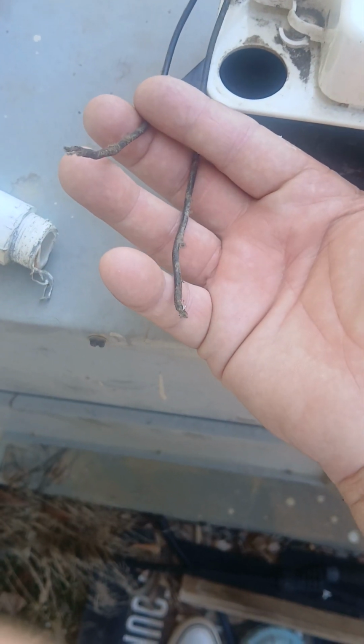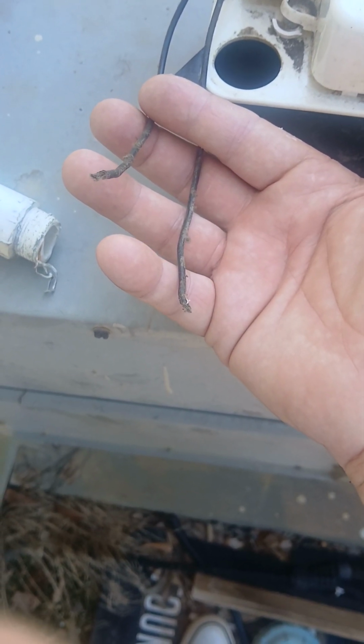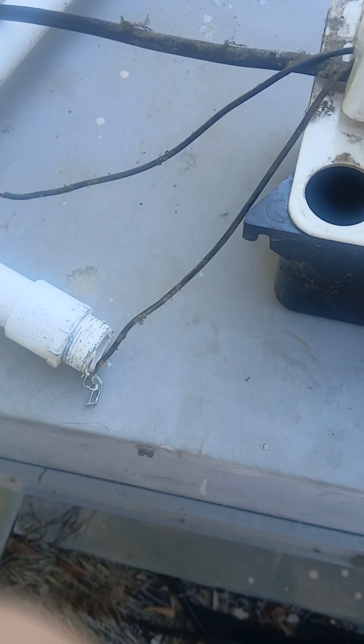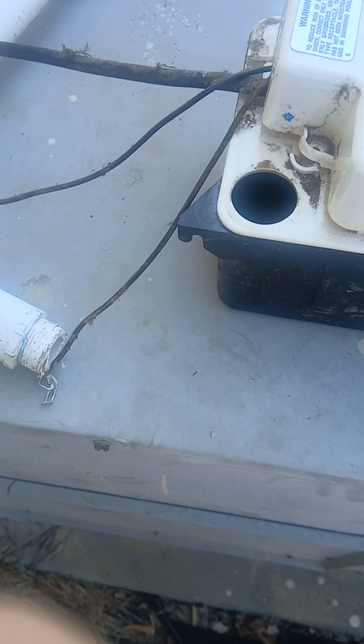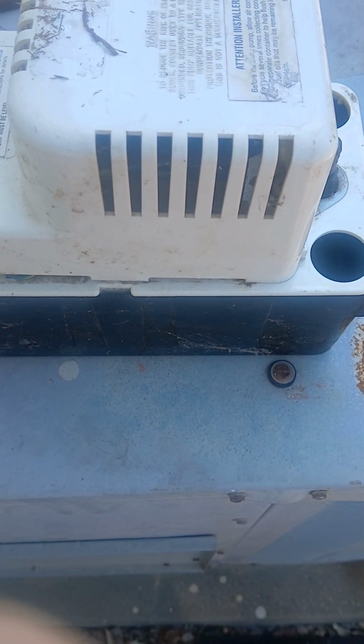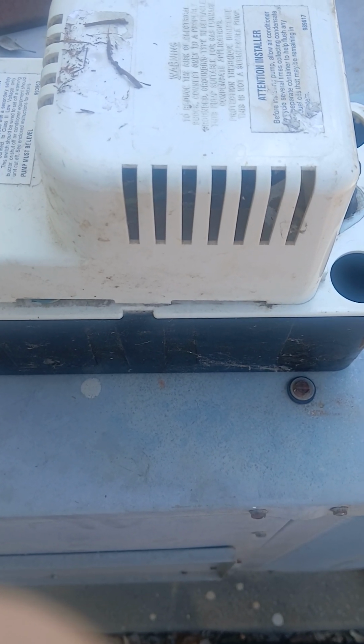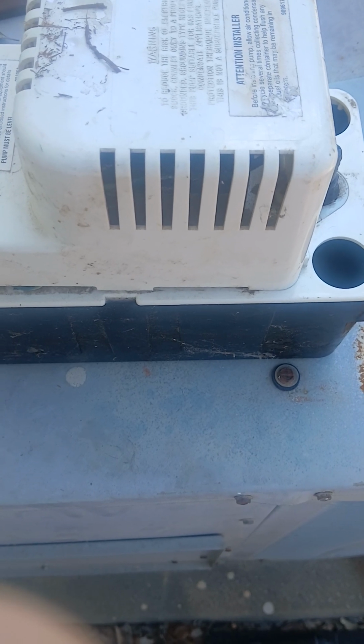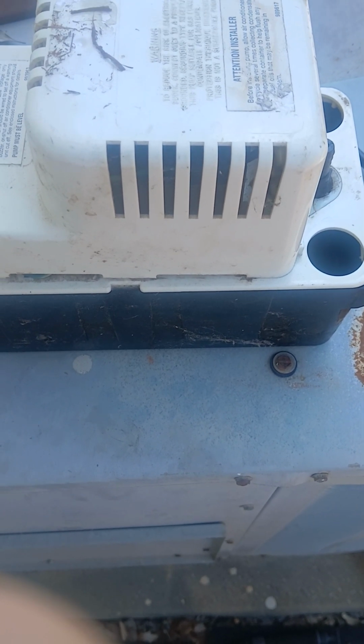And the HVAC guys can add this to the comments, whether you could use your yellow or not on this, going from, say hypothetically, your yellow out to your condenser. Because if you shut your condenser down outside, the compressor is not moving the refrigerant. Hence, if it's not moving the refrigerant, the A coil may not be getting cool. Hence, it may not produce any moisture. And when I say moisture, meaning water or water droplets, maybe the terminology is when the temperature is lower than the dew point. If the temperature becomes lower than the dew point, heat goes to cold. So then it develops like, say if you had a Pepsi Cola can and you started to see sweat on the bottom of that, but if it continuously runs and creates sweat, you need to get rid of it. That's what this is for.